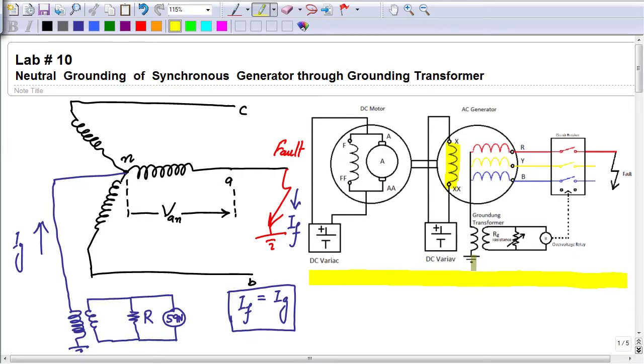And between neutral and ground we have the primary of the grounding transformer. On the secondary side we have inserted a grounding resistance RG. The value of this resistance is selected in such a way that it would limit the fault current in case of a line to ground fault in this range, 10 ampere to 35 ampere. This is the range in which fault current will vary, and according to the required value of current we insert the resistance on the secondary side of this transformer.